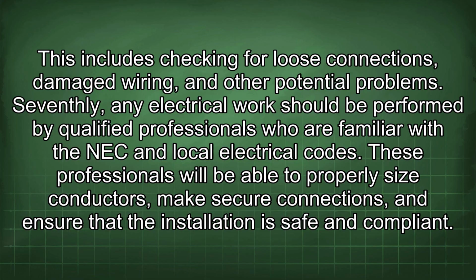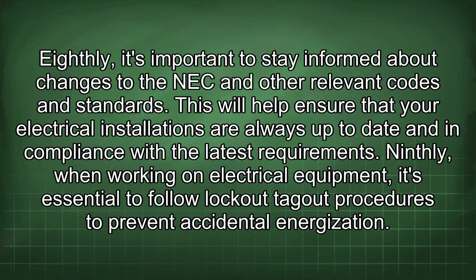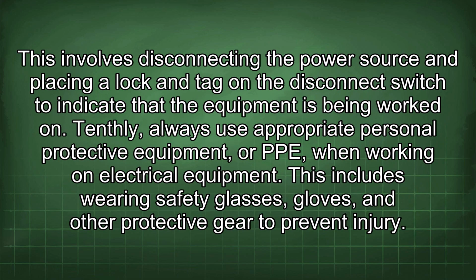Seventhly, any electrical work should be performed by qualified professionals who are familiar with the NEC and local electrical codes. These professionals will be able to properly size conductors, make secure connections, and ensure that the installation is safe and compliant. Eighthly, it's important to stay informed about changes to the NEC and other relevant codes and standards. This will help ensure that your electrical installations are always up to date and in compliance with the latest requirements. Ninthly, when working on electrical equipment, it's essential to follow lockout-tagout procedures to prevent accidental energization. This involves disconnecting the power source and placing a lock and tag on the disconnect switch to indicate that the equipment is being worked on. Tenthly, always use appropriate personal protective equipment, or PPE, when working on electrical equipment. This includes wearing safety glasses, gloves, and other protective gear to prevent injury.